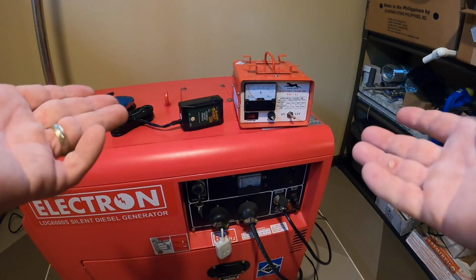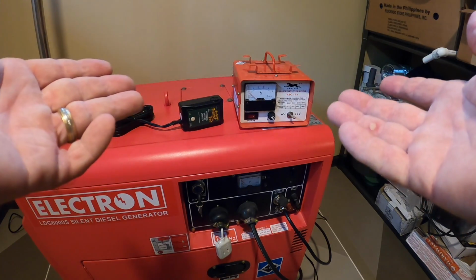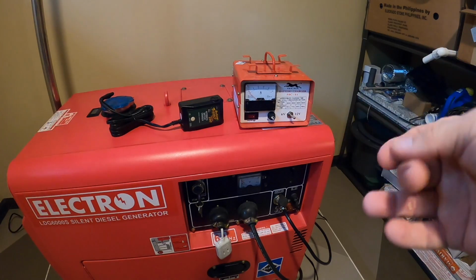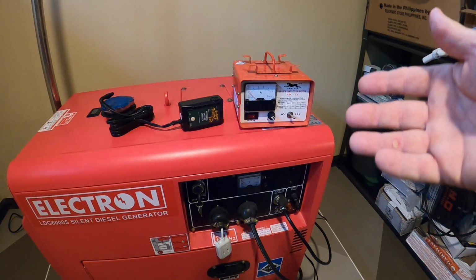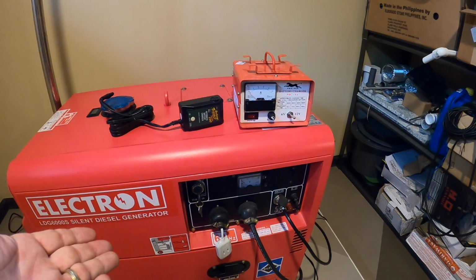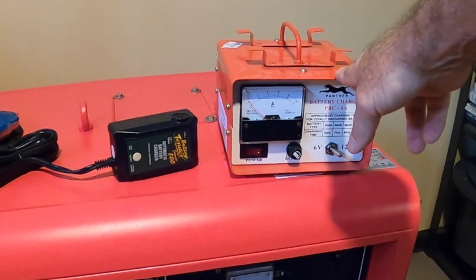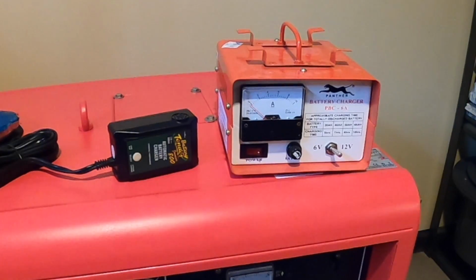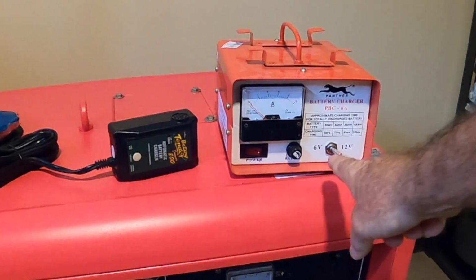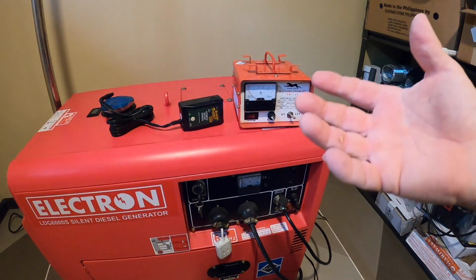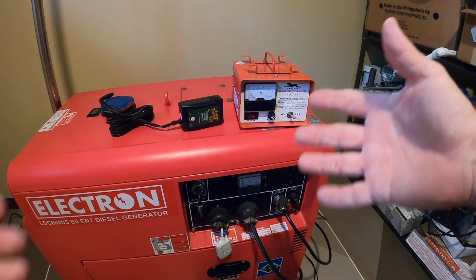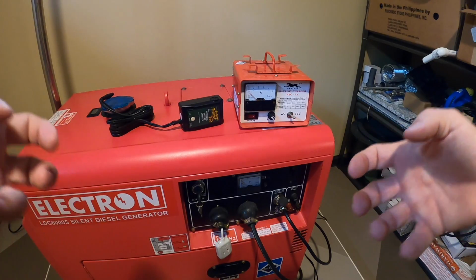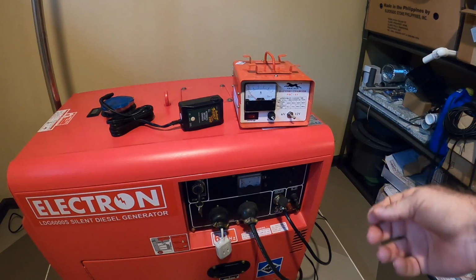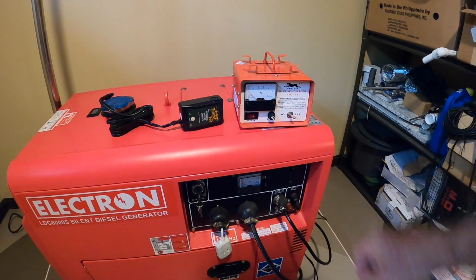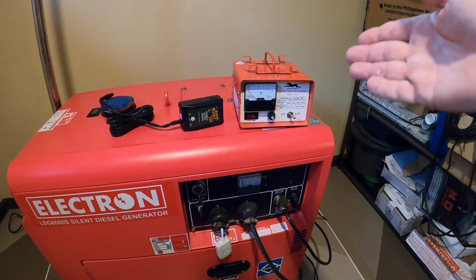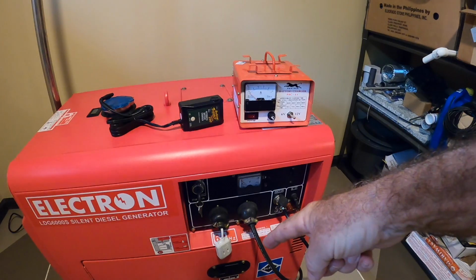If you have an emergency situation, or even a non-emergency situation where you want to keep your system and batteries as healthy as possible, especially for long-term storage situations where you don't use it very often -- which often happens with a gen set -- I have a battery charger I picked up from Handyman. It's the Panther battery charger, model PBC-6A, and it works for both 6-volt and 12-volt systems. Depending on the capacity in amp hours, the charge takes longer -- it's mainly for bigger batteries like inside a truck, say a 60 amp. But a standard battery, like a 30 amp, will take a very short time to charge, and that's what I used for the gen set down here.